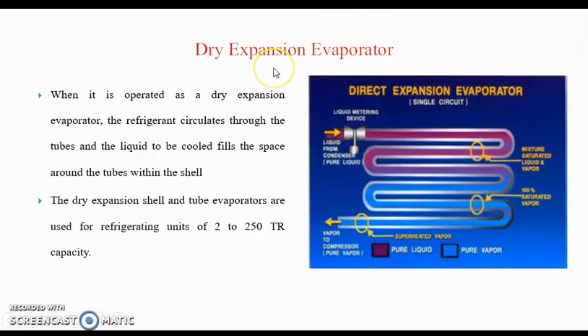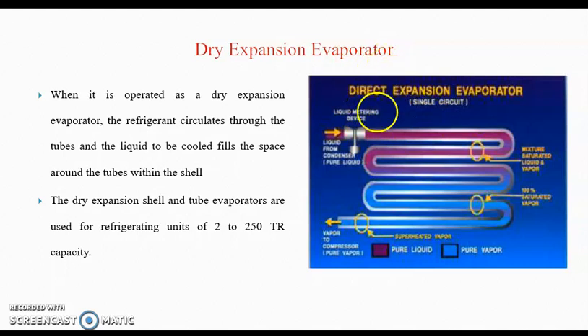The first is the dry expansion type evaporator. In the dry expansion type evaporator, the refrigerant circulates through the tubes and the liquid to be cooled fills the space around the tubes within the shell. So the refrigerant flows inside the tubes and water flows surrounding the tubes. This dry expansion shell and tube evaporator is used for refrigerating units from 2 to 250 tons capacity.